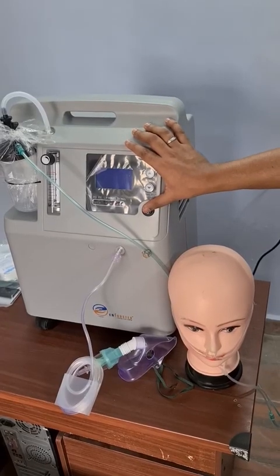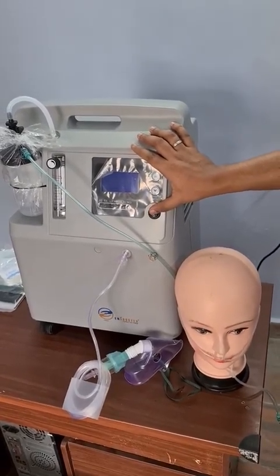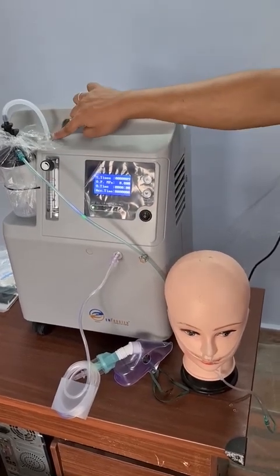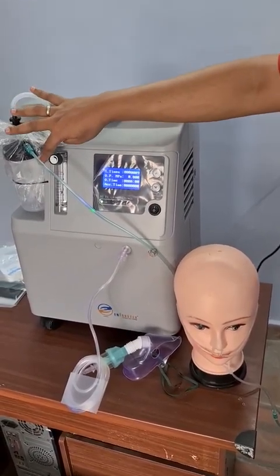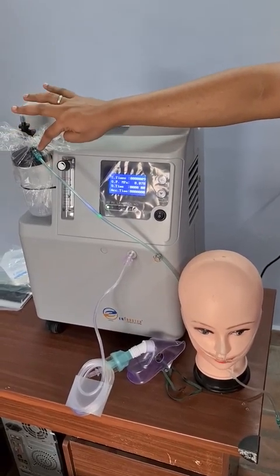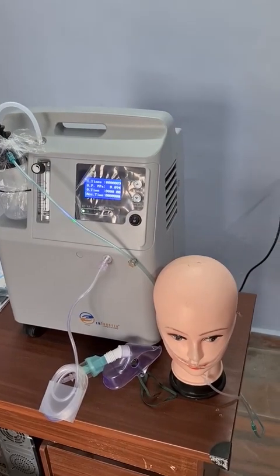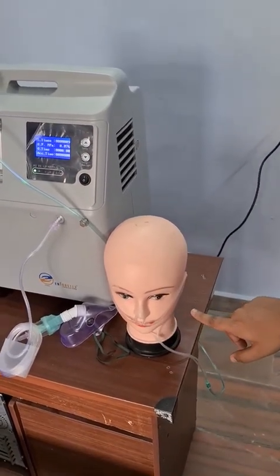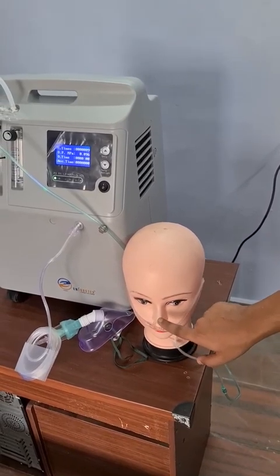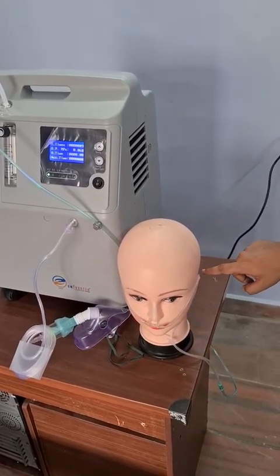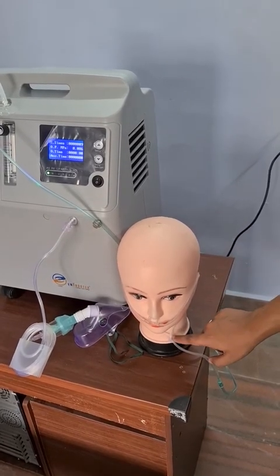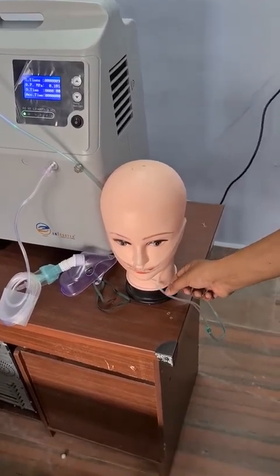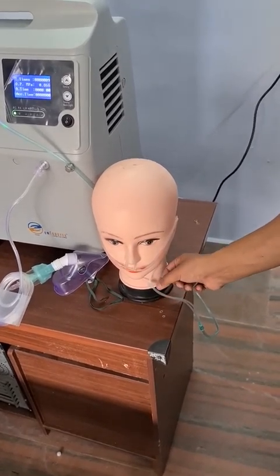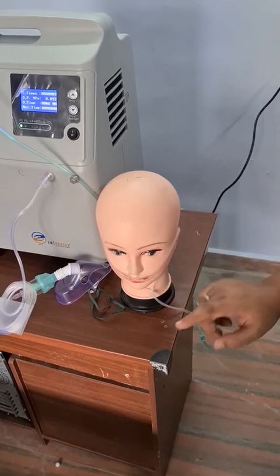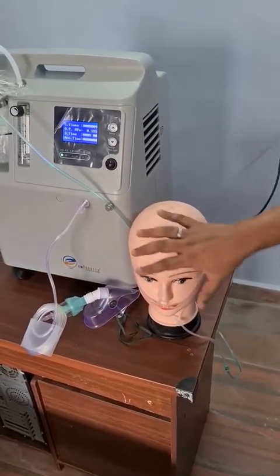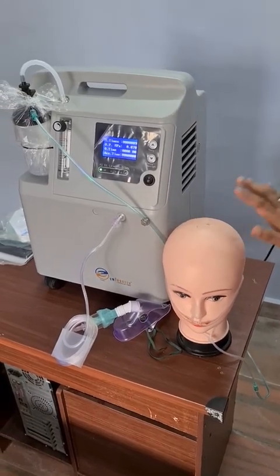I am going to show you the proper way of connecting the nasal cannula to the patient. So I have switched on the device. Oxygen is getting outputted. It is going through the humidifier. It is taking the water. It is getting humidified. And from this output port, it has to go to the patient using a cannula. The proper way to connect the cannula, just see on the mannequin. You can see the two nasal prongs are going inside the nostrils, and it has to be aligned in such a way that it goes around the ears, so that there is a lock for adjustment. As per the comfort of that particular patient, you can adjust it and make sure full oxygen is going into the nostrils. That will benefit the patient. So this is the proper way of connecting the nasal cannula to the customer.